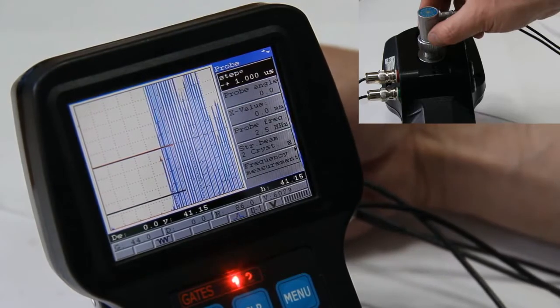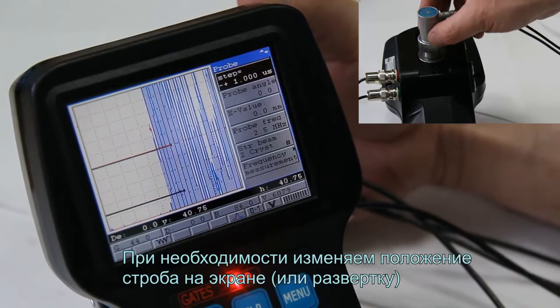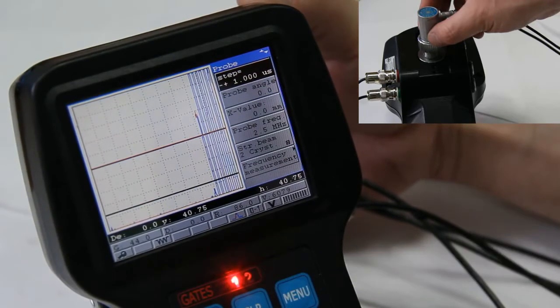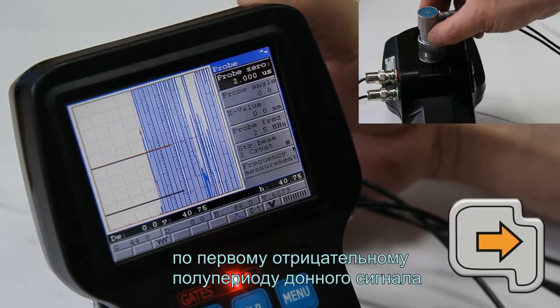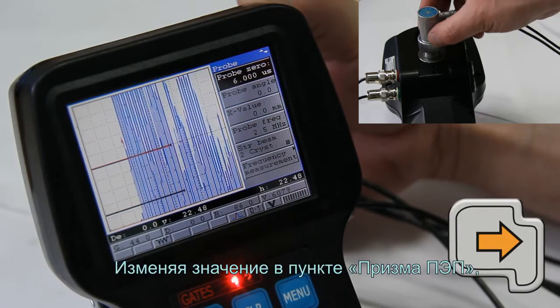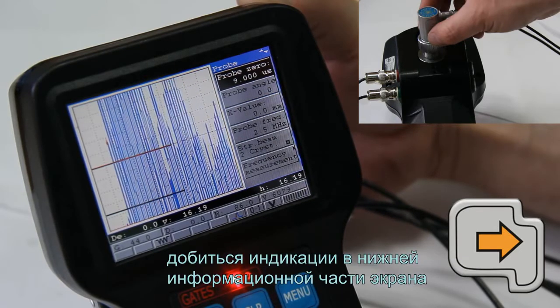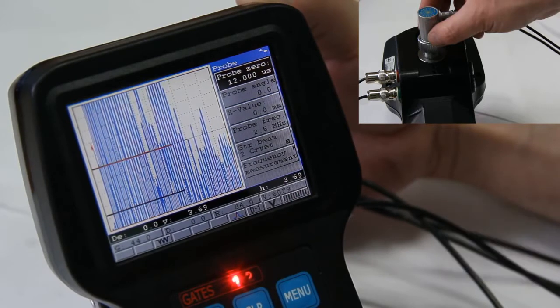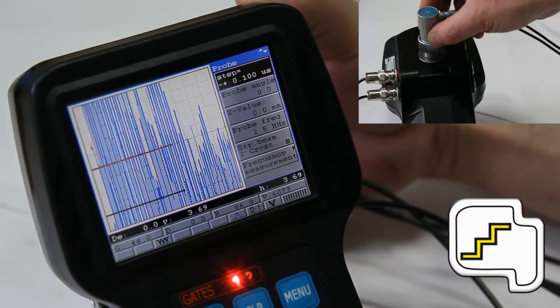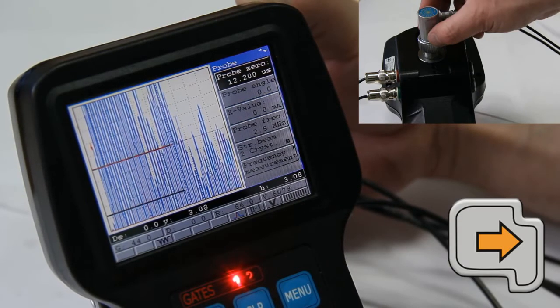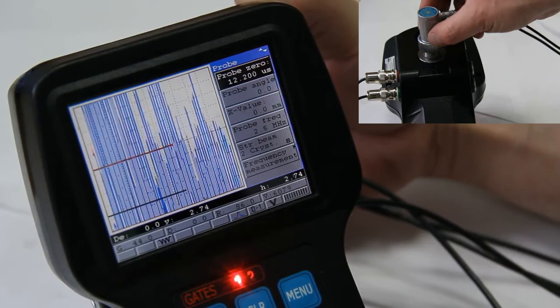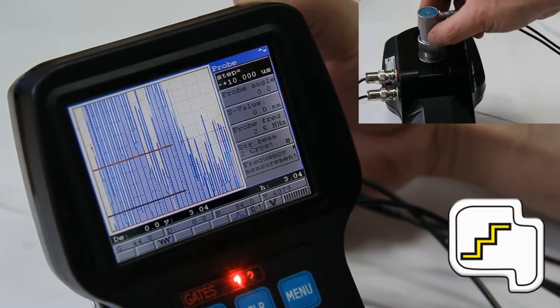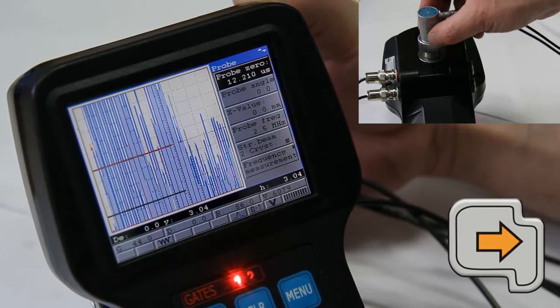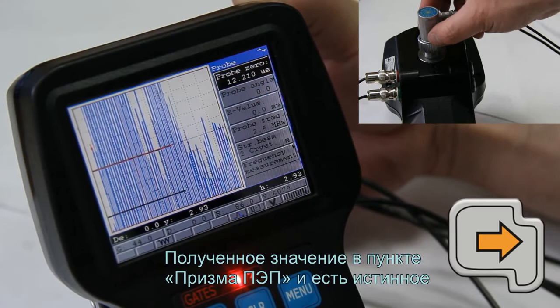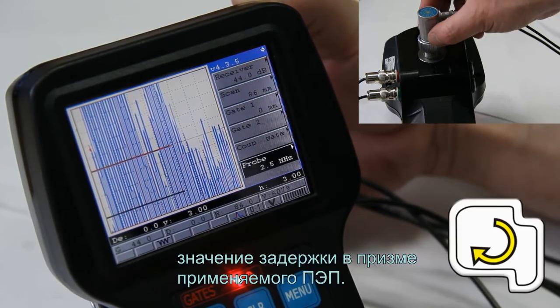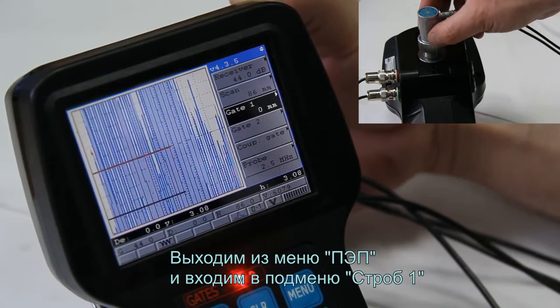If required, change the probe position on screen or the scan position and achieve the first backwall echo to be within the gate. When changing the gain, achieve the measurement to be carried out by the first negative half period of a signal. When changing the value in the probe 0 item, achieve the real block thickness to be indicated in the bottom information panel of the screen. The received value in the probe 0 is the true value of the delay in the probe of a used probe. Exit the probe menu and enter the Gate 1 submenu.